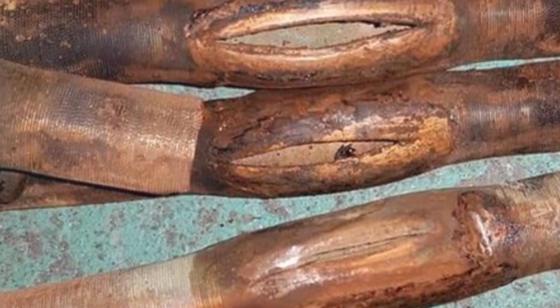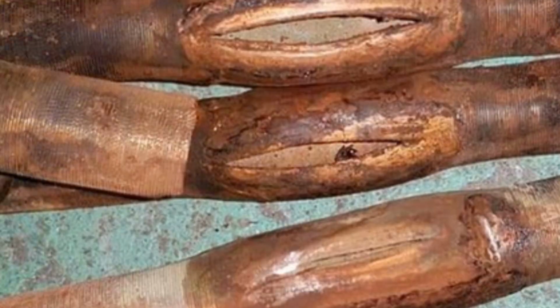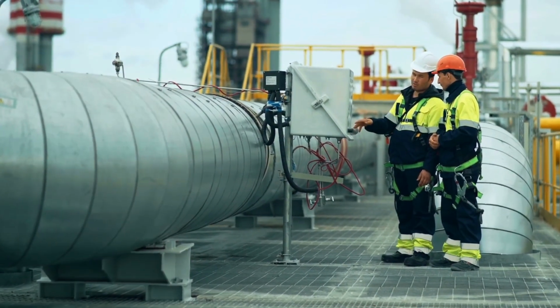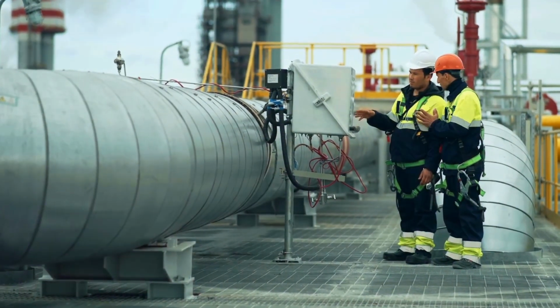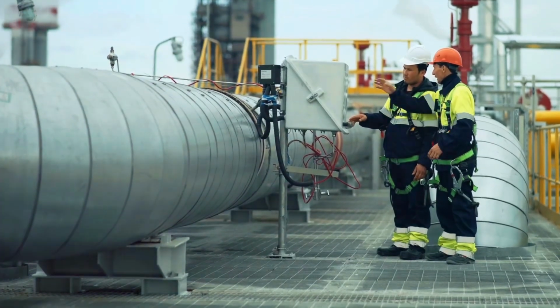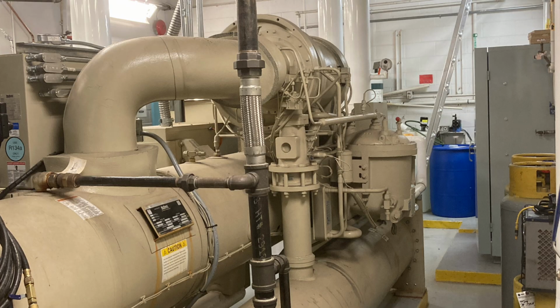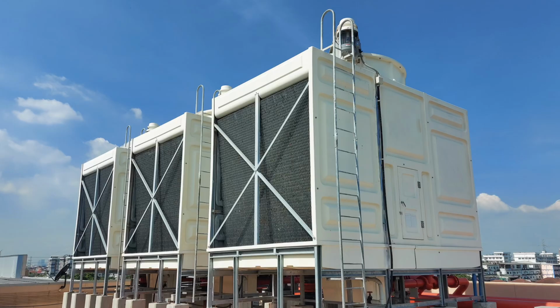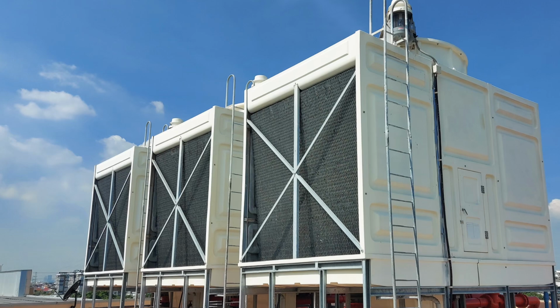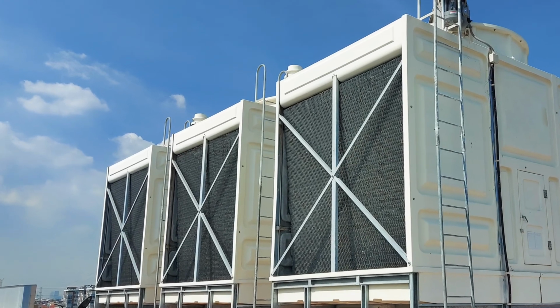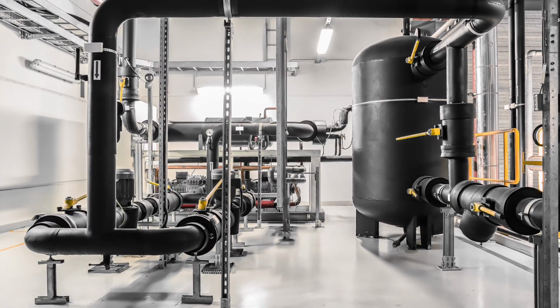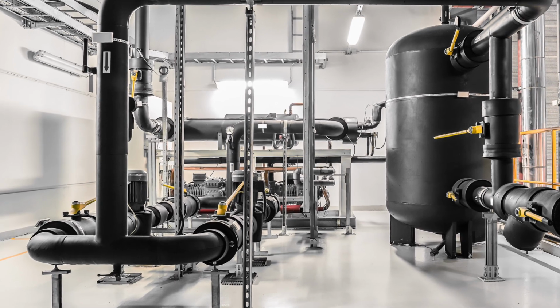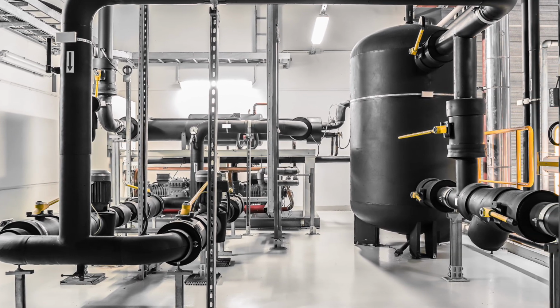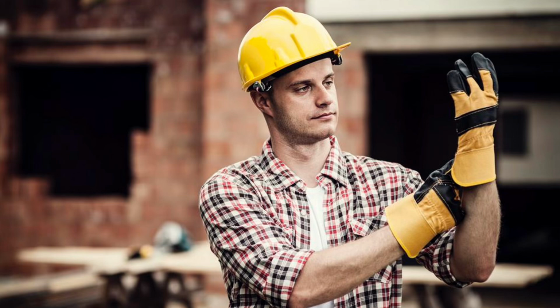It's extremely important to note that if you make a mistake, you could freeze the machine and rupture your tubes. I've worked with many guys who have frozen up tubes on the machine before because they overlooked something or got in a hurry. It happens, we all get in a hurry sometimes and make mistakes. That's why it's so important to make sure you're trained when doing this, to minimize the possibility of damage or injury. Most manufacturers' training will talk about this but won't actually do it with the guys due to lack of time or resources. If you need to do this on a machine and this is your first time ever, it is not advised to do it by yourself.